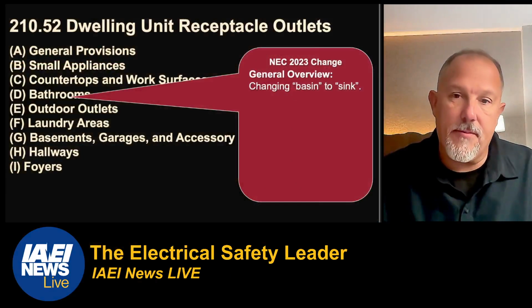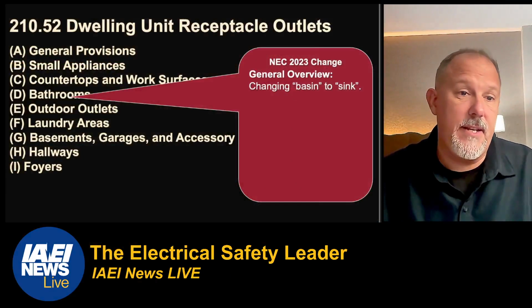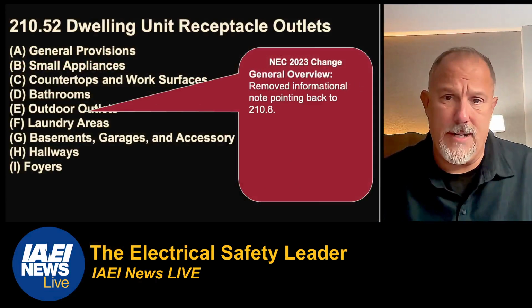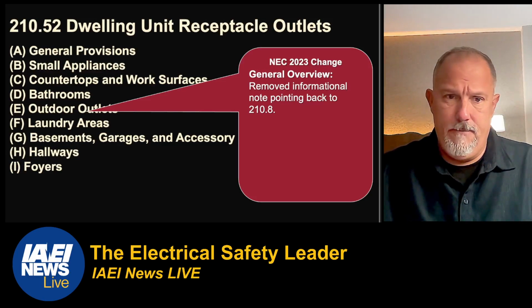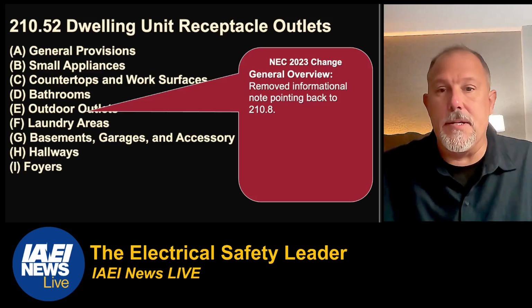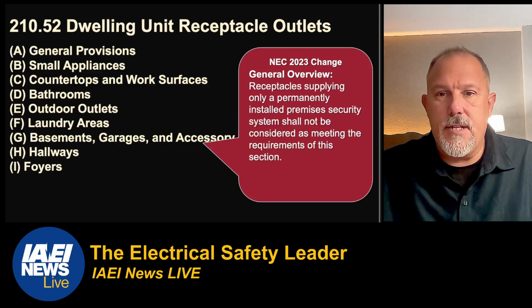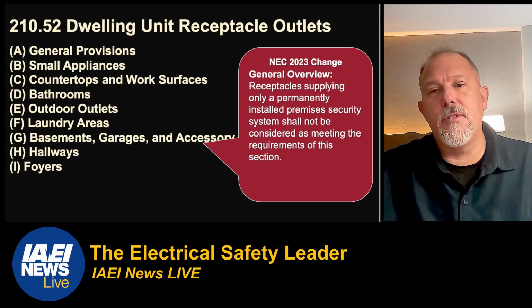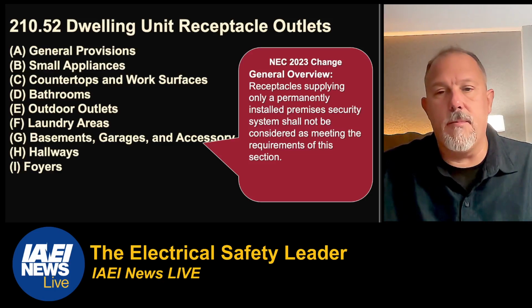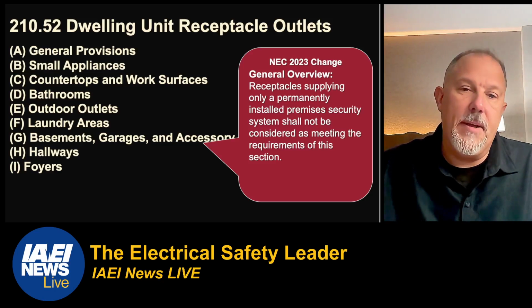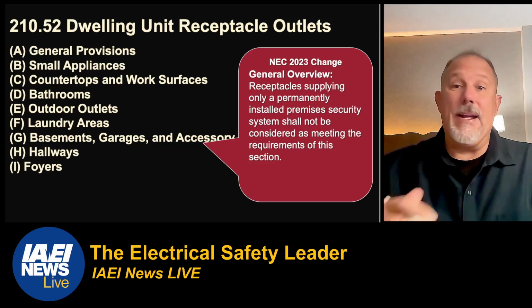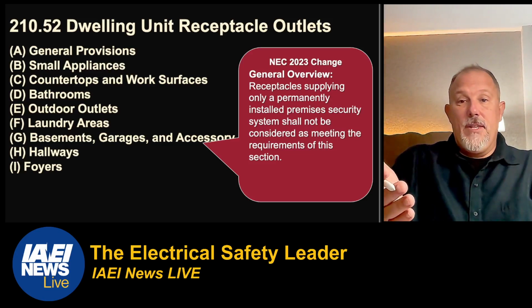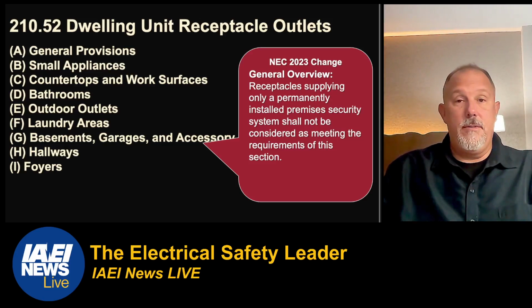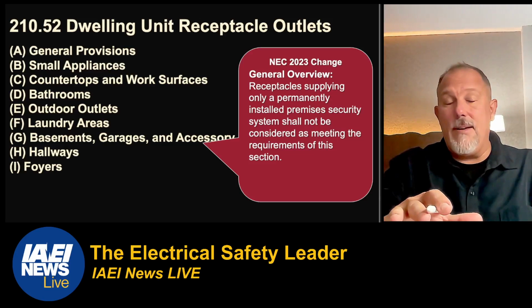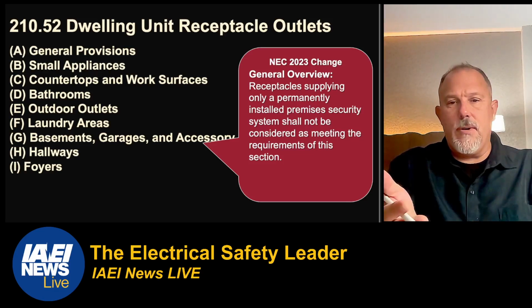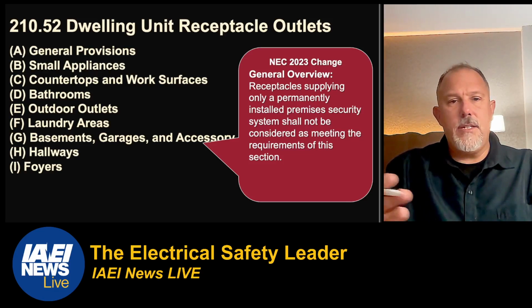So bathrooms, general overview, changed the basin to sink. Big deal? Not. We removed an informational note because it said it was duplicate. And then in basements, receptacles supplying only a permanently installed premises security system shall not be considered as meeting the requirements of the basements, garage, and accessory buildings. But in reality, as we said, a premises security system can be in any room. So we would really have to take a look at that one again, because why is it just basement, garages, and accessory buildings? Why isn't it just in the general provision?